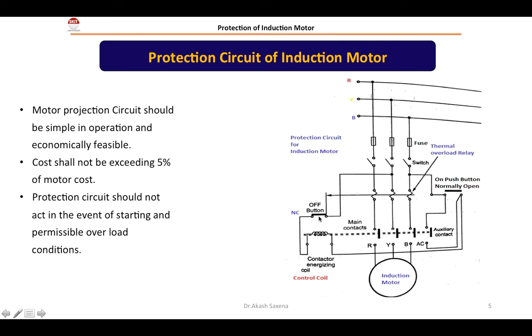When the start button is pressed, the contactor coil is energized as it gets supply voltage. The coil attracts the plunger, and the induction motor gets the supply. Even if the start switch is released, the contactor coil remains energized as it gets supply through the auxiliary contact. Thus the motor starts running.